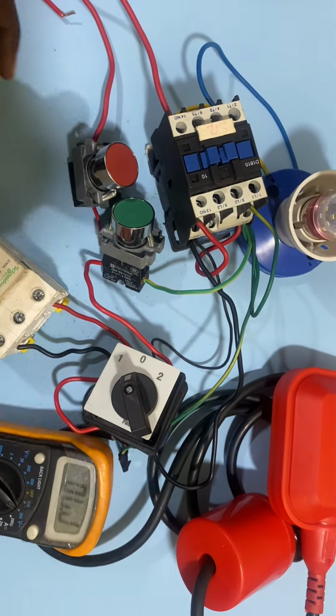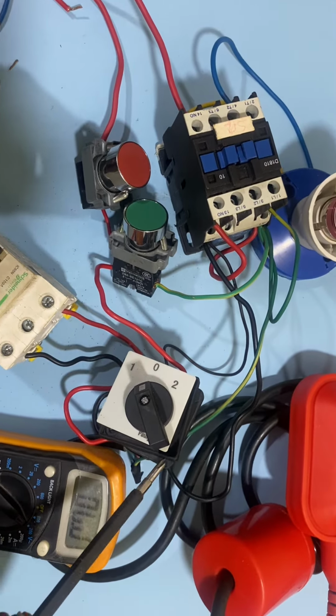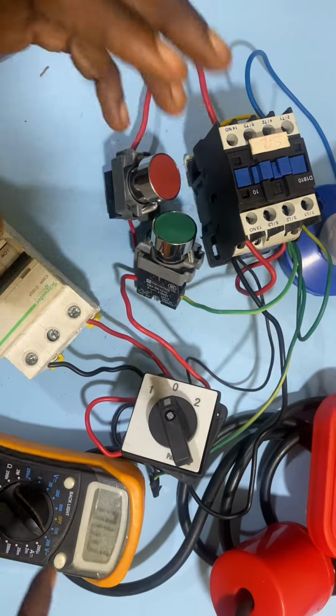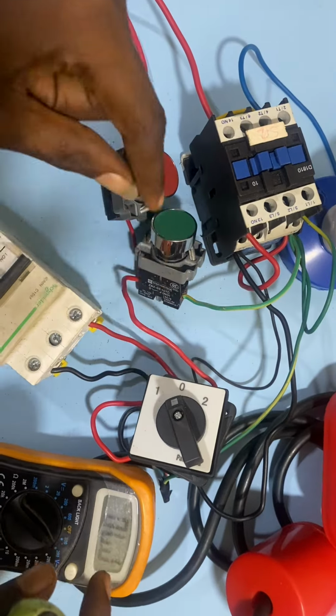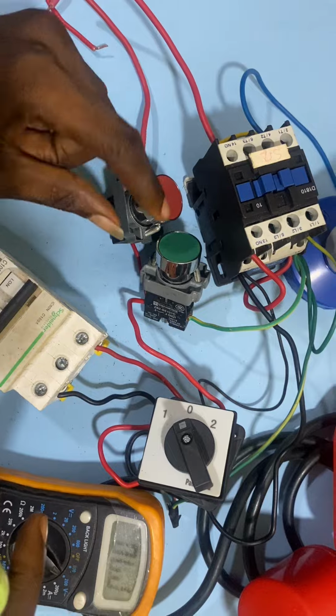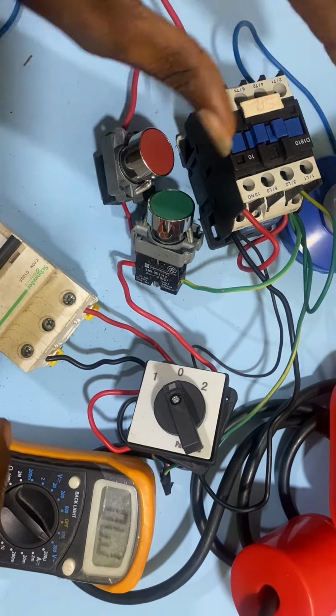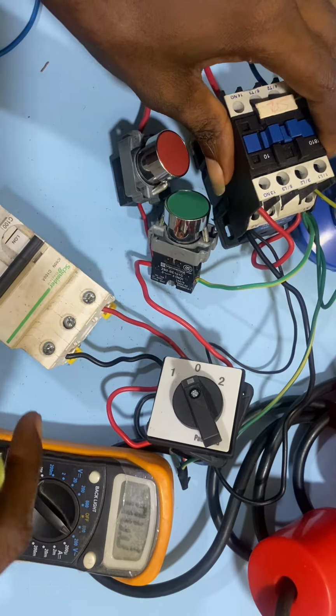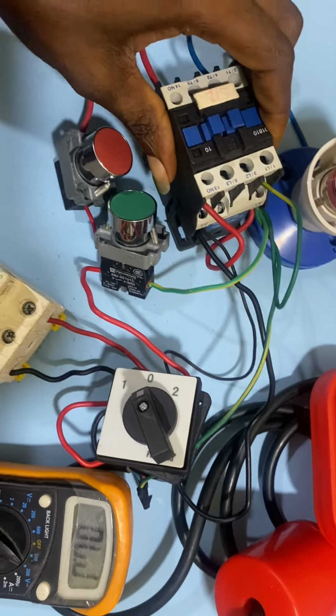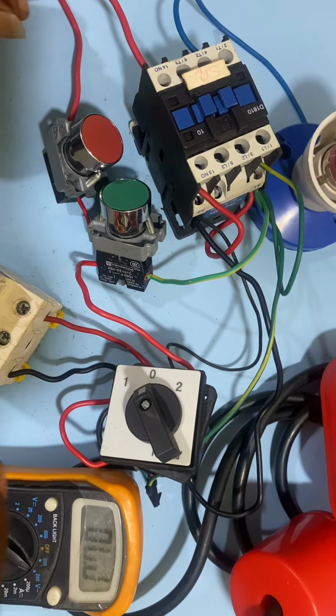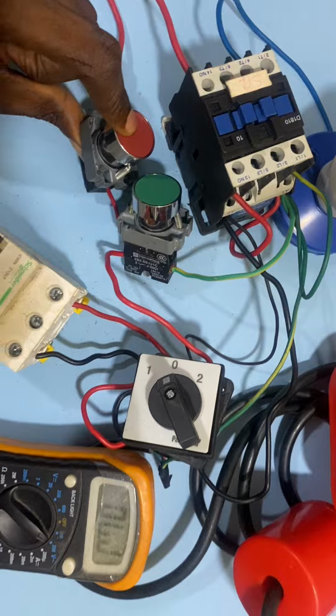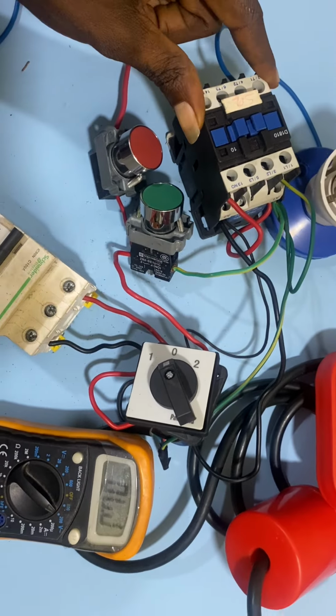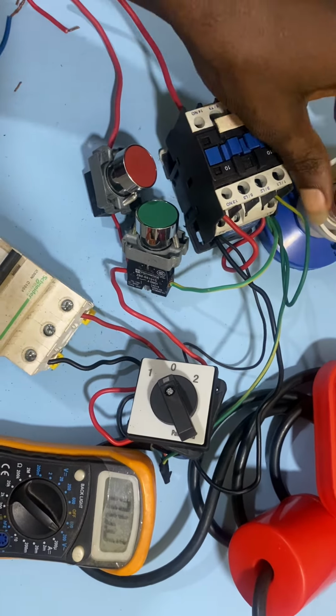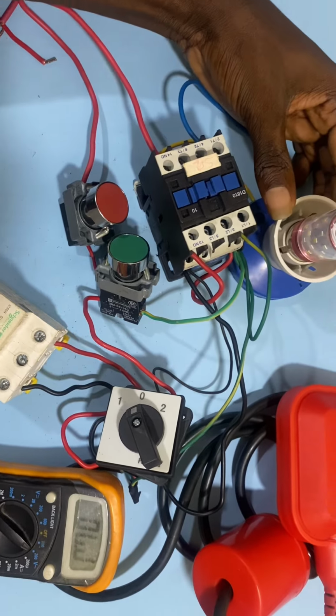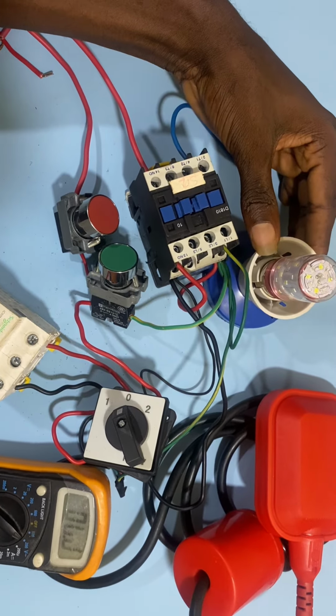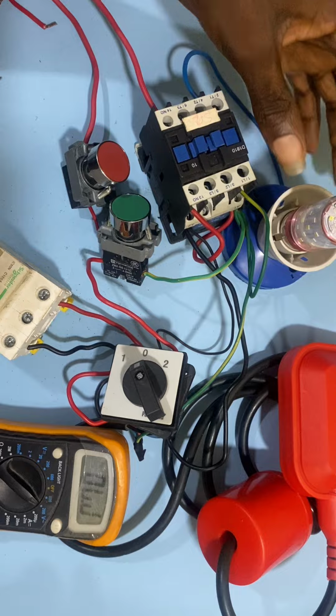See, we are done with all the connection, and the selector switch here is at position one, meaning that I want to manually start pumping the water by clicking the start button, which energizes the coil of the contactor, and to manually stop pumping the water by clicking the stop button to de-energize the coil of the contactor which our load is connected to. And our load is always our pumping machine, but in this case I'm using this AC bulb. So in your own case, you connect your pumping machine to where we are connecting the AC bulb.